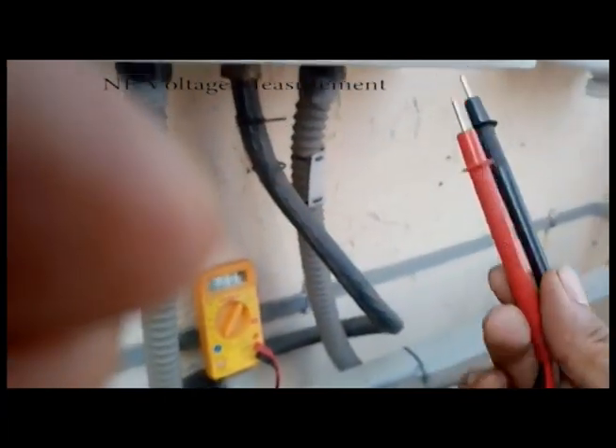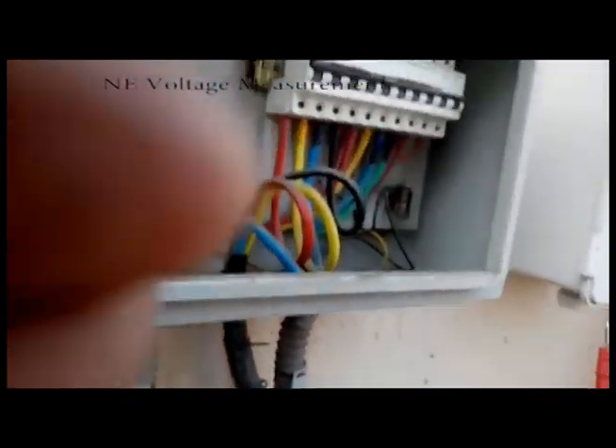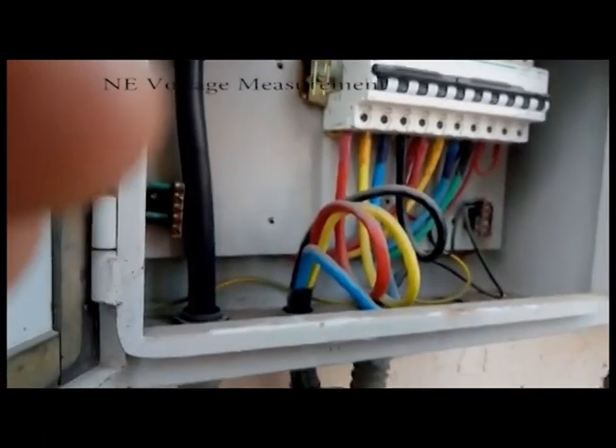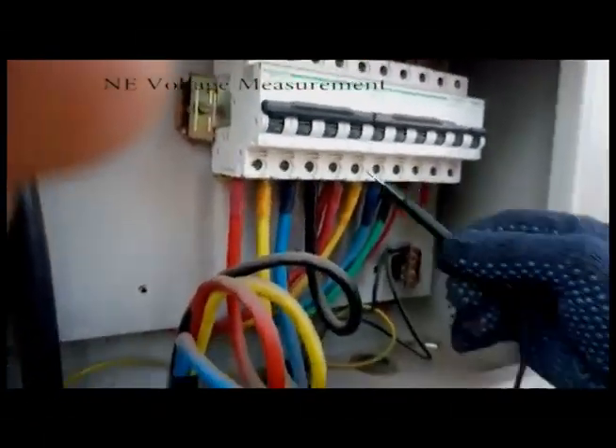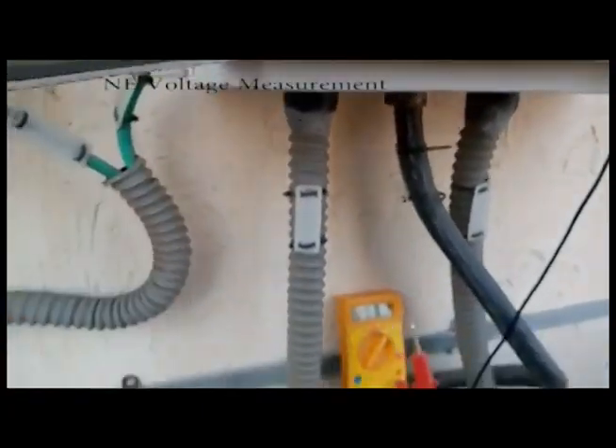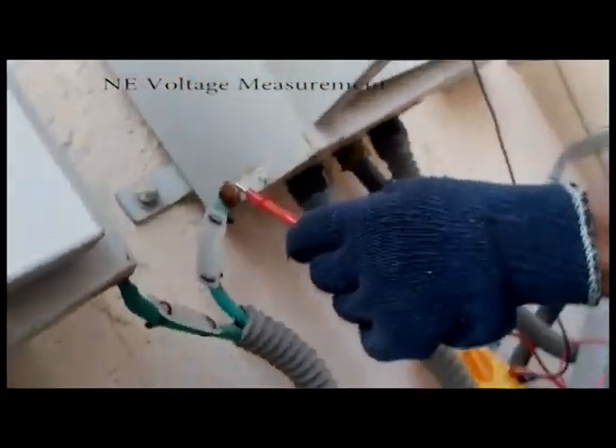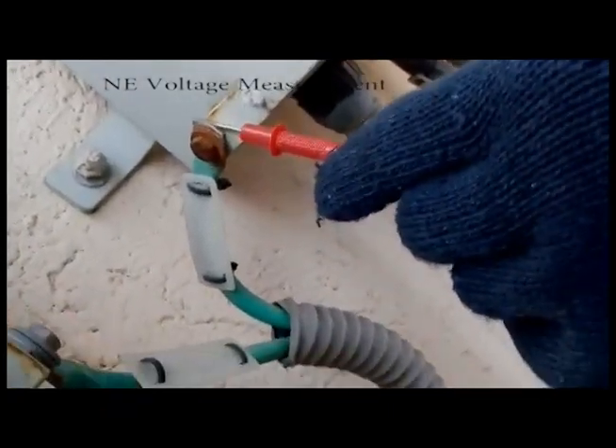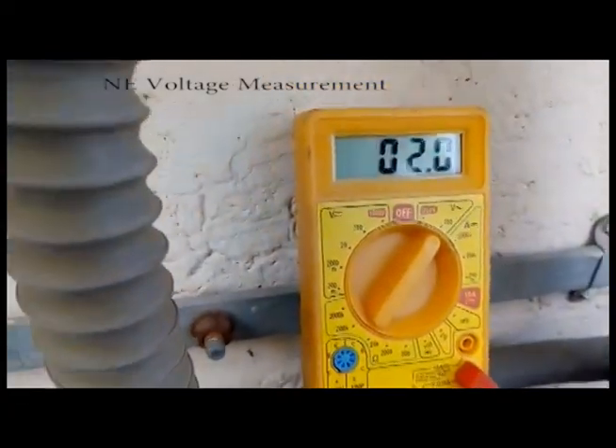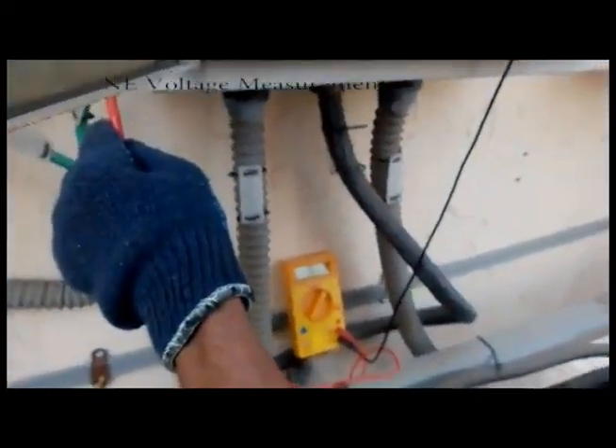Now we are going to check N-E (neutral-to-earth) voltage — it should be less than 5 volts. One end is kept on the neutral cable and the other end is kept on the earthing port where the earthing cable is connected. We are going to check the value, and as you can see here: 2.0, 2.1.